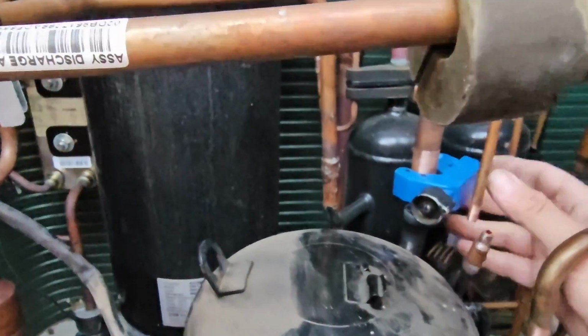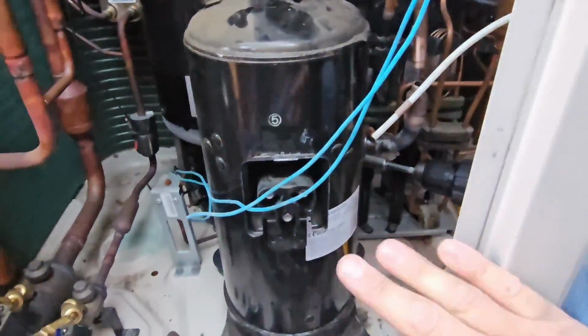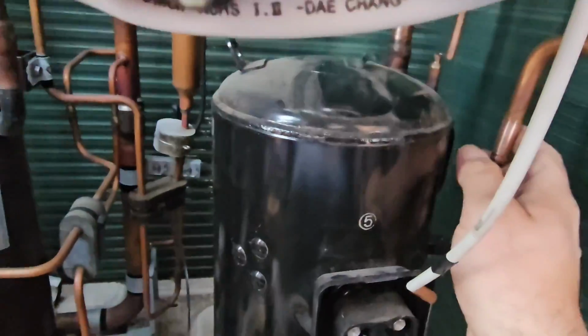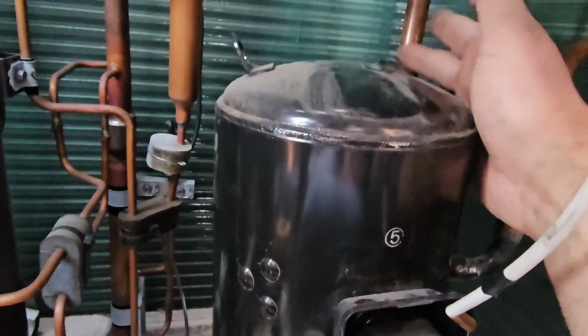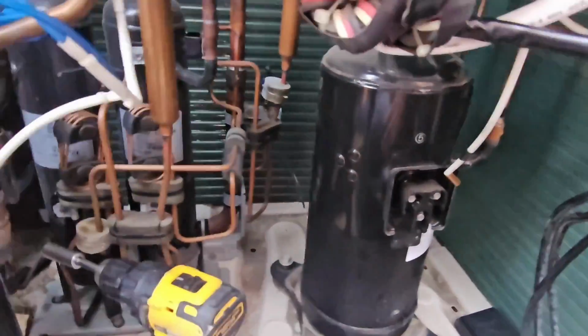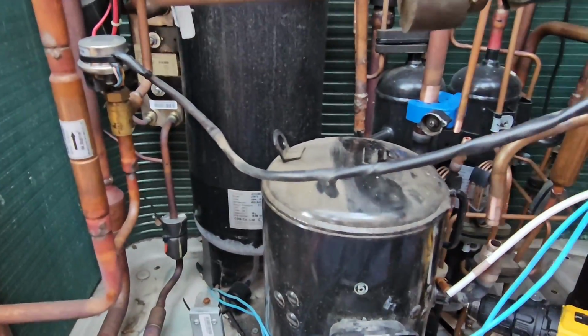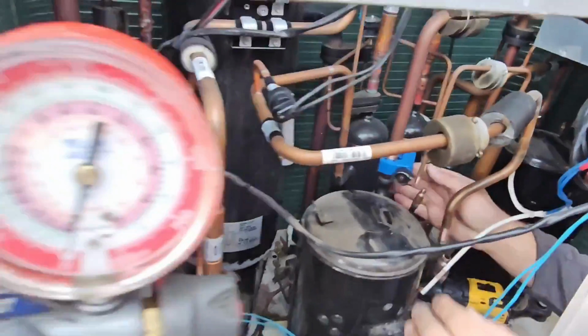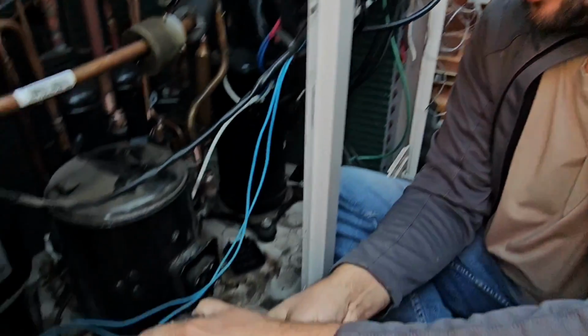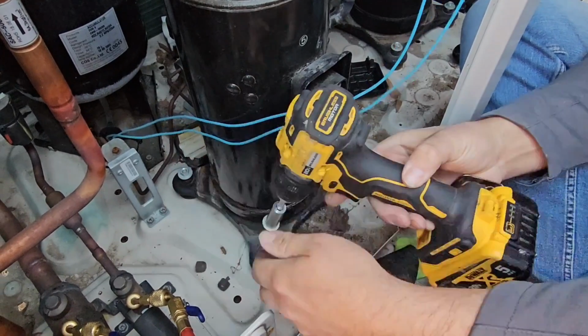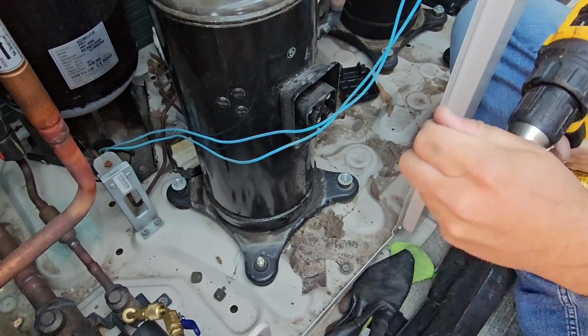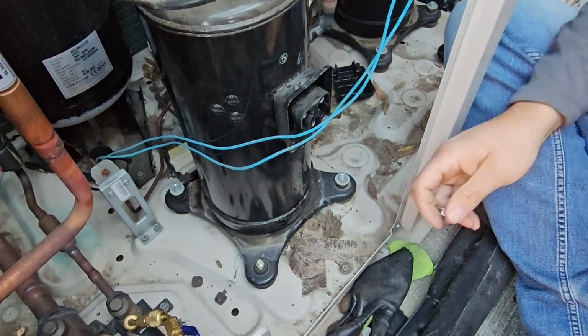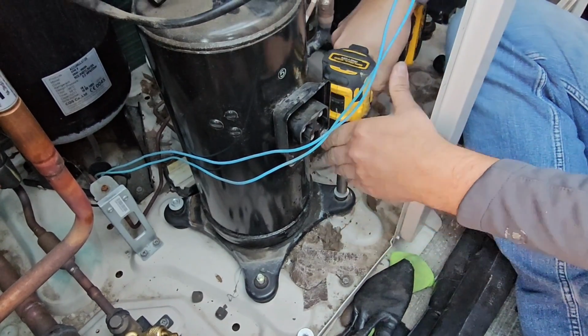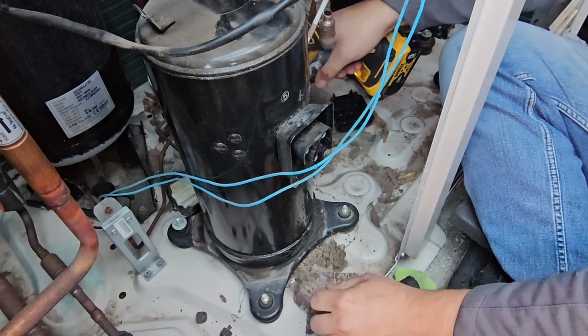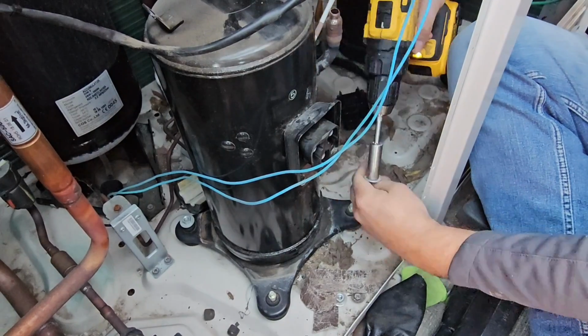So I'm going to cut this pipe here, and then this compressor will be ready to take out. And then I've got 1 more pipe to cut for this compressor. Same pipe, suction pipe. Let me get those cut, and then we'll work on the next step. Now we're going to use the 1/2 inch socket that I've got connected to the drill, and we are going to take all of these nuts off of the bolts that go through the feet of the compressor. That way we can take this old compressor out.